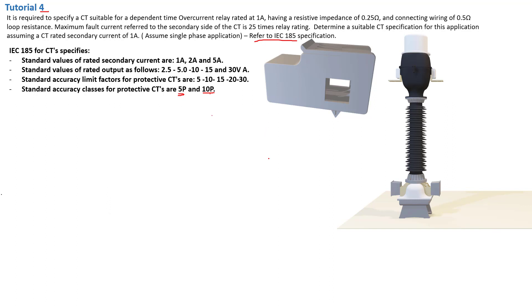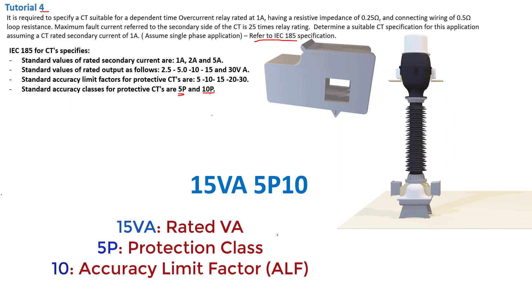At the end of this tutorial, we're going to select a current transformer that looks something like this: 15 VA 5P 10. That basically means 15 VA is the rated burden, 5P is the protection class, and 10 is the number of times that multiplies the rated current before the CT reaches saturation. This is a standard representation of a current transformer.